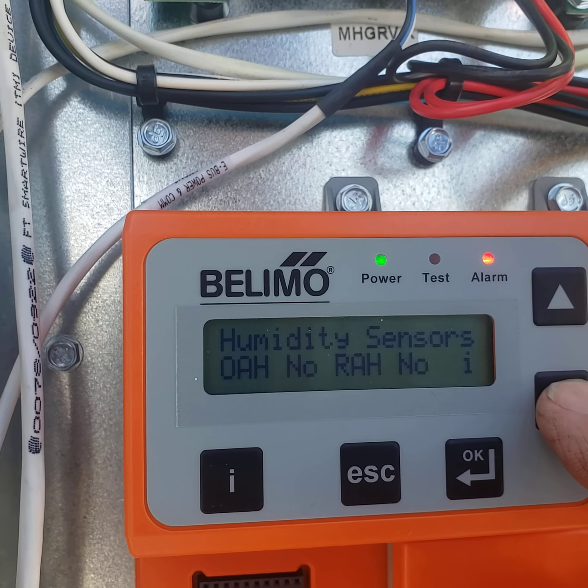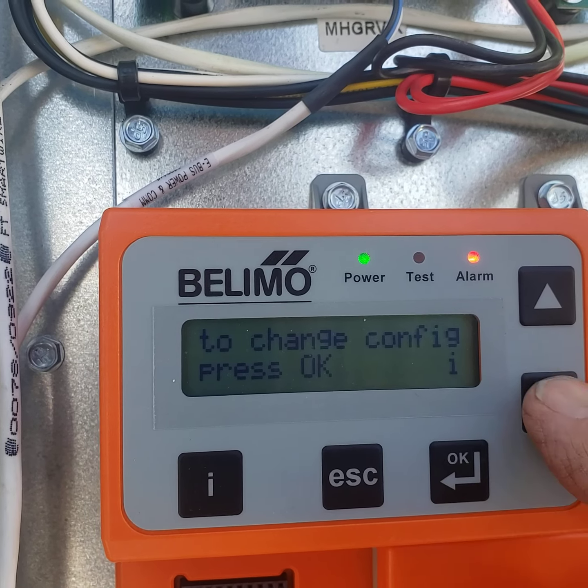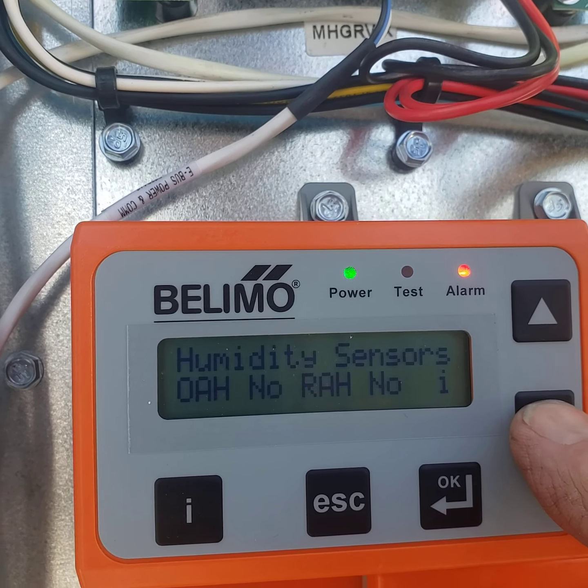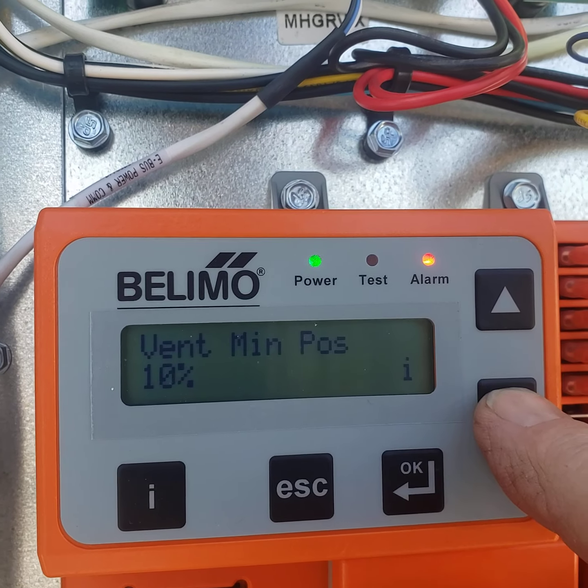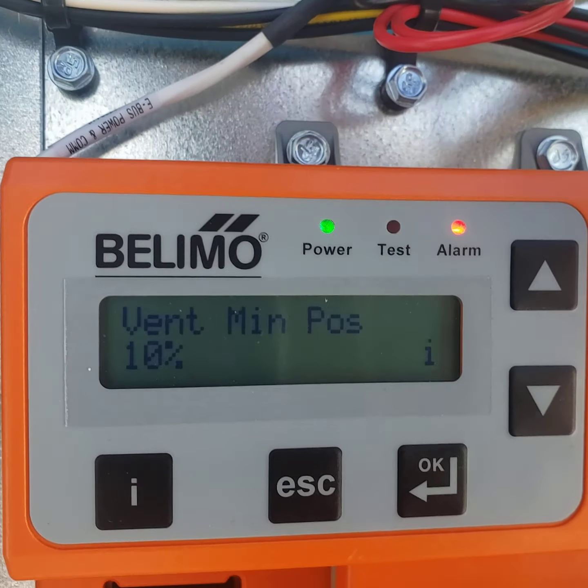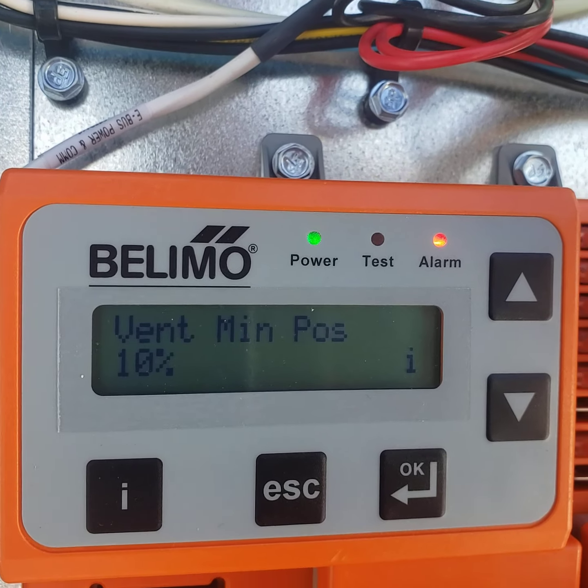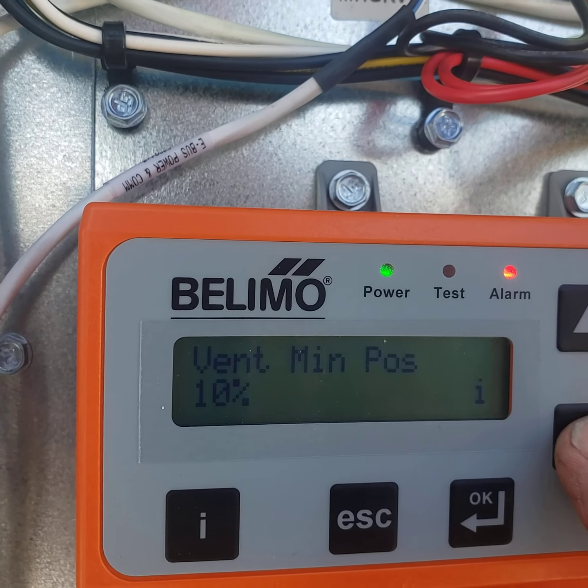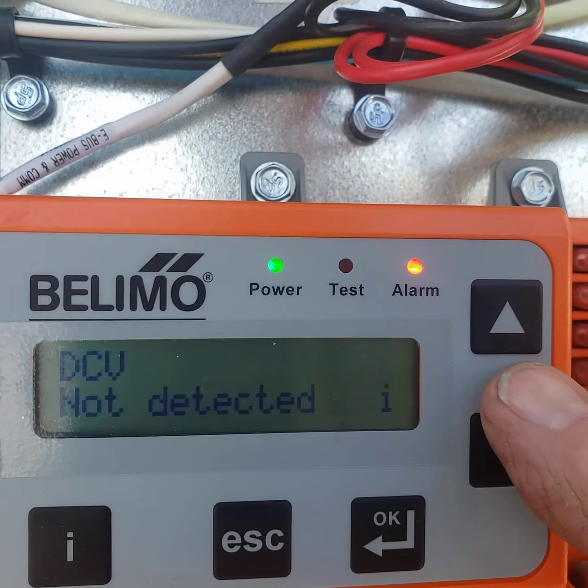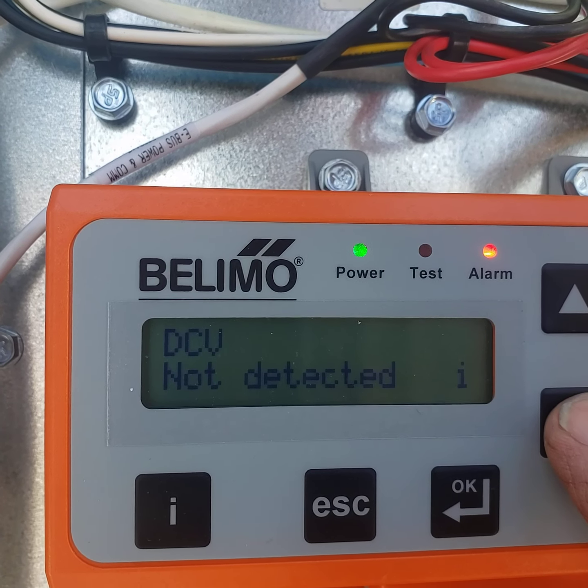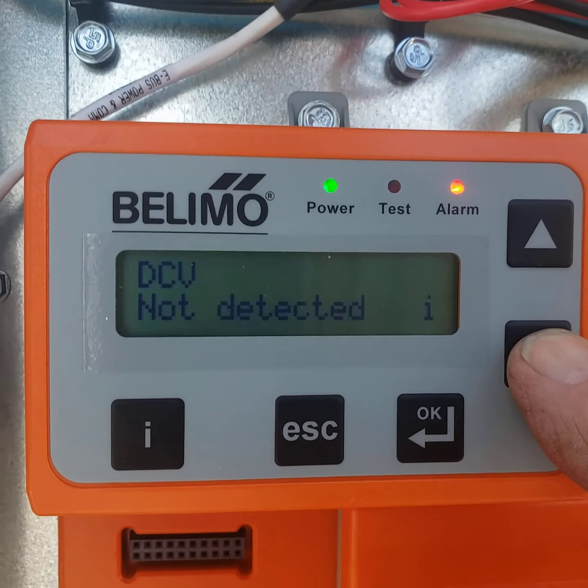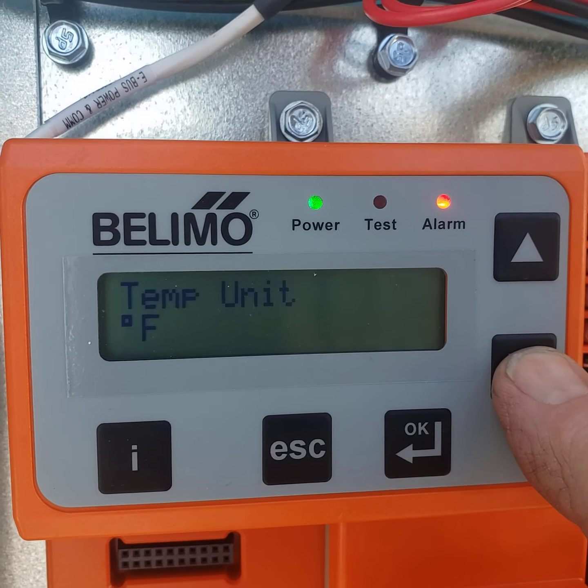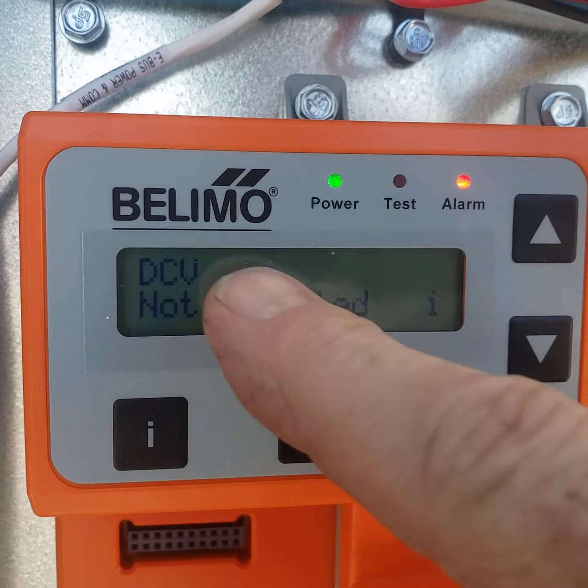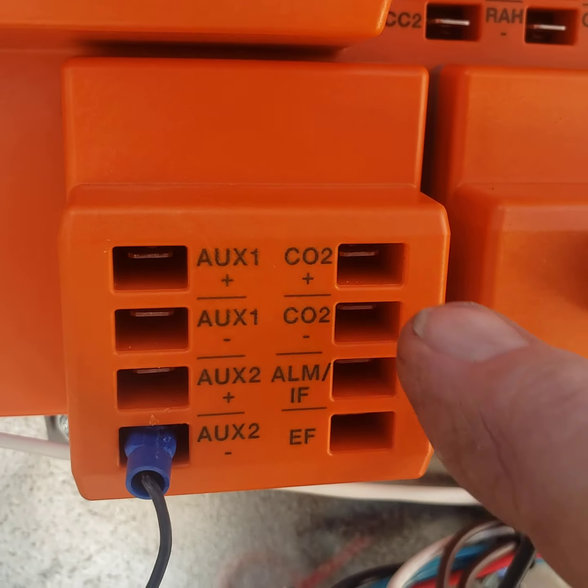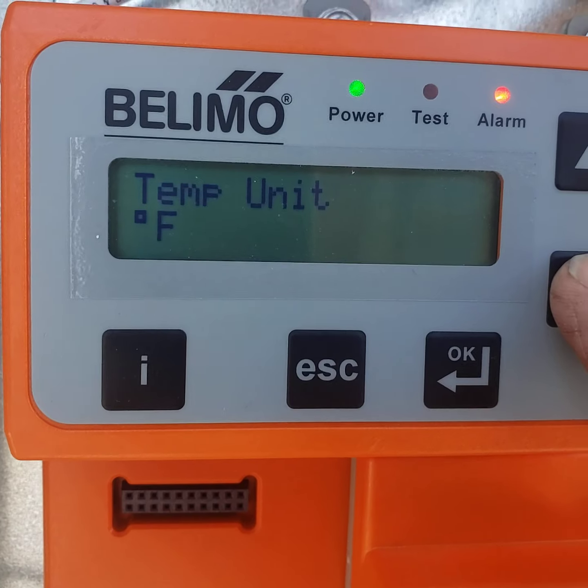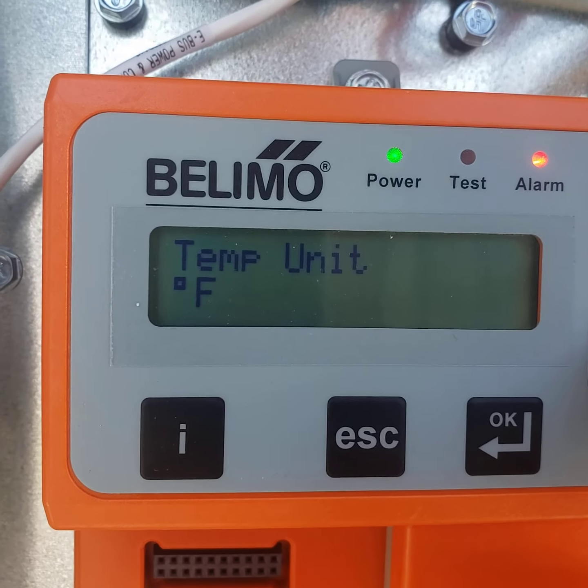Humidity sensors we don't have, and we didn't change anything there. They were auto detected, or not detected in this case. Vent position, that's the other setting you'll need to change. So your zip code and your vent minimum position, whatever you'd like to put in there. I'll just scroll through the rest of these items. Demand control ventilation, like CO2 sensing and alarming, we don't have that here. If you did have it, it would auto detect, because it would be landed right here and it would say detected. Temperature, Celsius or Fahrenheit.